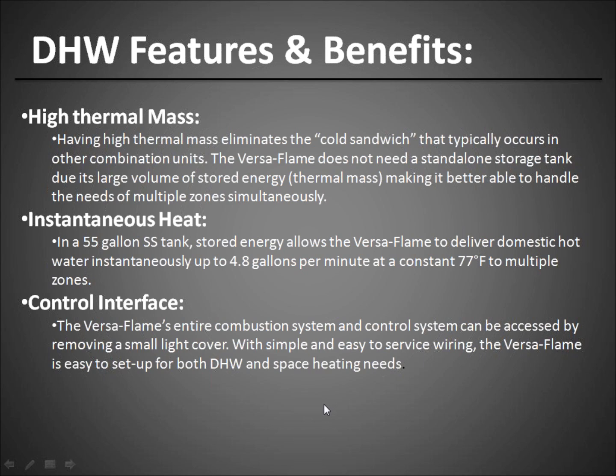All right, guys, we're going to get into some of the features and benefits of the VersaFlame. The VersaFlame, as most of you know, is a combination system where we provide heat and hot water with one appliance. One of the major features of this product, which is essentially an offshoot of the Pioneer, is its thermal mass. We have a large thermal mass on the heating side, which eliminates a lot of problems associated with short cycling, eliminates primary, secondary pumping, makes the installation really, really easy for the guys who've had a lot of customers installing Pioneer. On the DHW side, what it does is it eliminates any cold sandwiching relating to what you would normally hear in the tankless market.